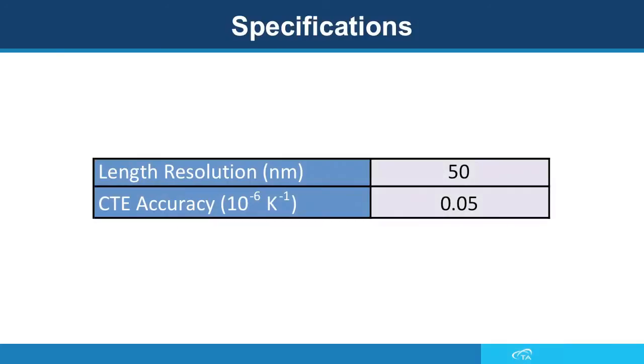Like all TA instrument dilatometers, the DIL806 is extremely sensitive, accurate, and precise, with length resolution as low as 50 nanometers and CTE accuracy well below one part per million per degree.